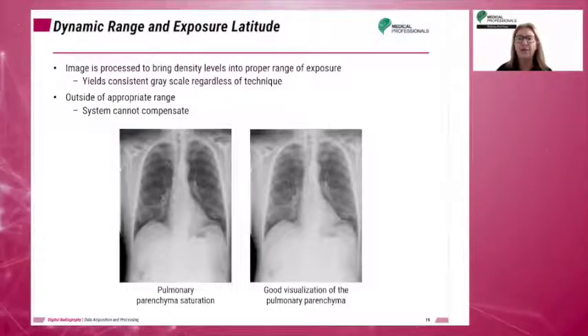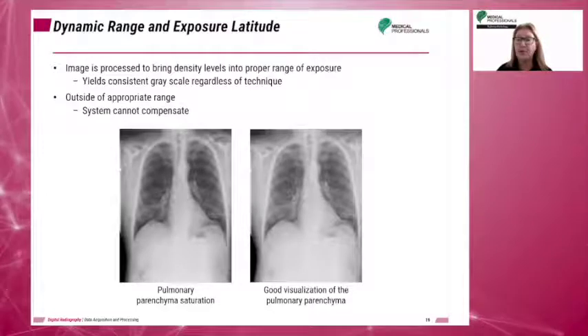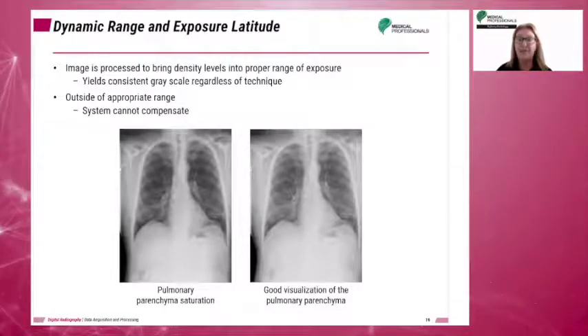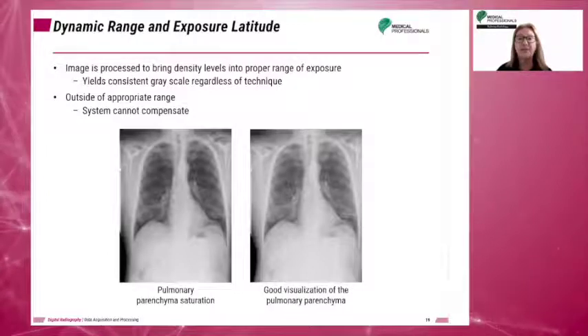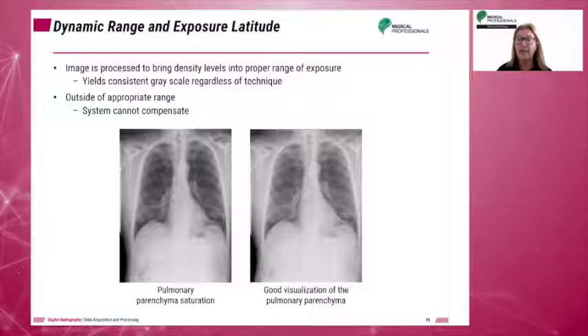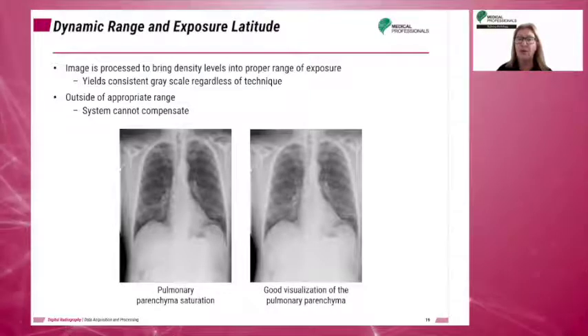In film screen imaging, an error in selecting mAs by as little as 30 percent is noticeable, and a 50 percent error usually requires a repeat image. In digital imaging, the system can tolerate as much as 60 percent underexposure and as much as 500 percent overexposure.